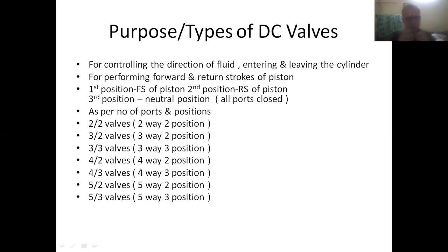Among these valves, two-way and three-way valves are only suitable for controlling single acting cylinders. And four-way and five-way valves are only suitable for controlling double acting cylinders.